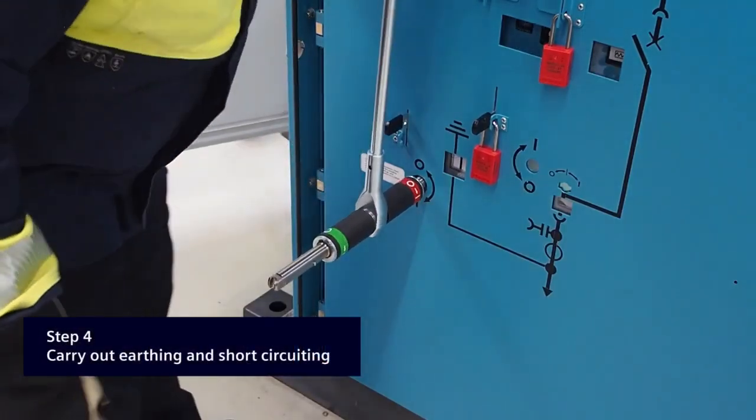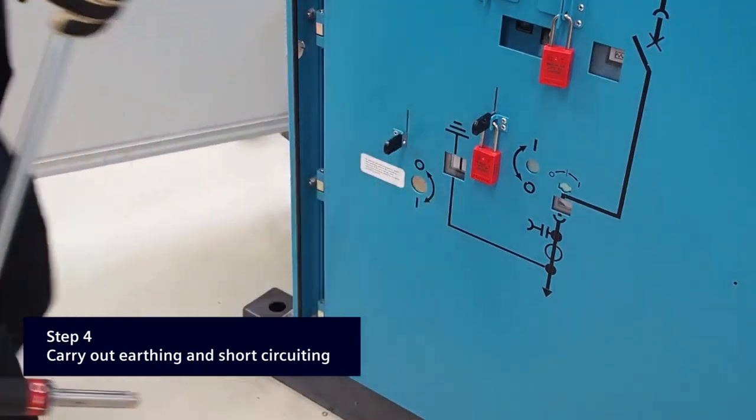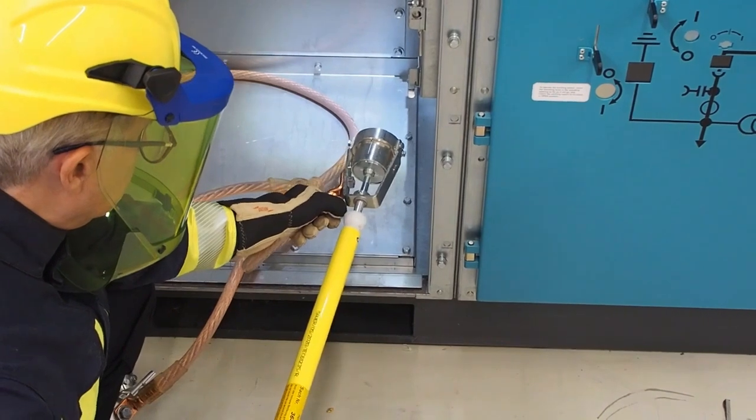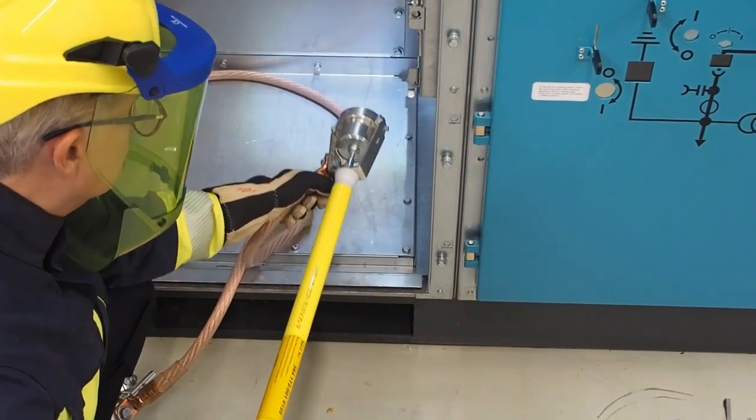The fourth step is to ensure that the bus bar and feeder are earthed. You can do this by using the Switchgear Earthing Switch or, if none exists, with a portable earthing kit.